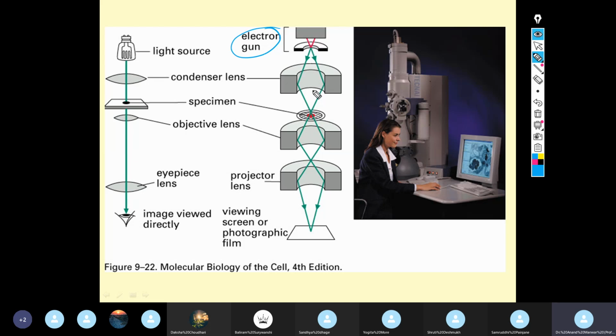that electron beam is focused. So here the condenser will condense, again it will channelize, and this electron beam will be bombarded on the specimen sample. Here the specimen sample is kept like this. Then after the specimen sample is the objective lens, in case of a light microscope, and here the magnetic objective lens is there. In place of the eyepiece, I said, there is a projector lens. The projector lens is also called the intermediate lens, and then the image is projected by the projector lens on the viewing window or viewing screen.